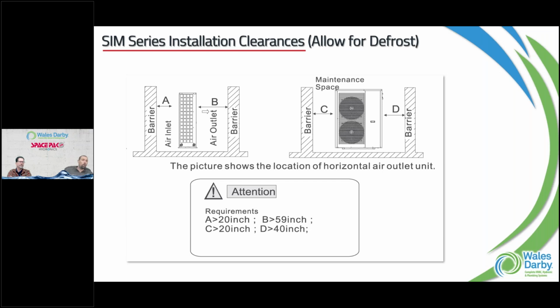Being a heat pump, we always talk about clearances. So whether it's air to water or refrigerant, they're important for us. We talk about heat exchange. We talk about heat transfer, right? If I don't have the airflow around the unit, then how do I collect the energy, or reject the energy there? That's it. So clearances are key. I know in some places there might be some challenges, or maybe it was clear when you did the install, but now the homeowner comes back and puts a wall in front of it and puts all their bushes and trees and all of that stuff. There could be a drop in performance, and that might be why.